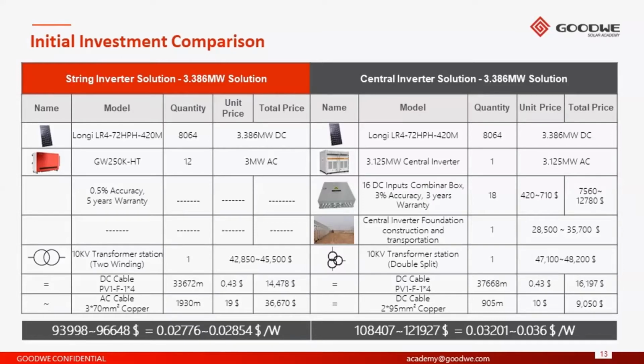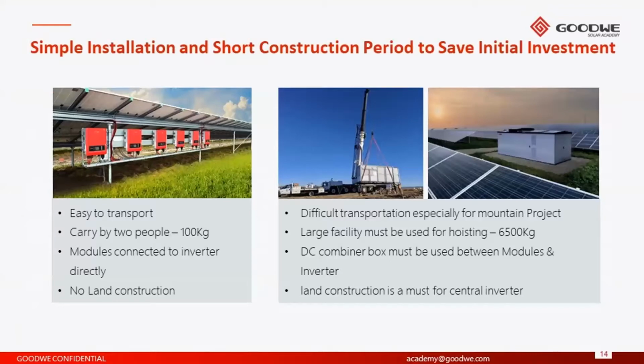When we do the maths and we take into account the balance of system components, which includes the DC combiner boxes and the installation and the transformers and the cables associated, it does look very attractive for a string inverter solution. As you can see at the bottom there, the dollar per watt is much lower than a centralized solution. But again, as a designer, as an engineer, what it comes down to is the appropriateness of the solution, along with the cost. There are a number of other advantages with string inverters: because we're dealing with a lot of smaller string inverters, the transport and the handling is much easier and much simpler.